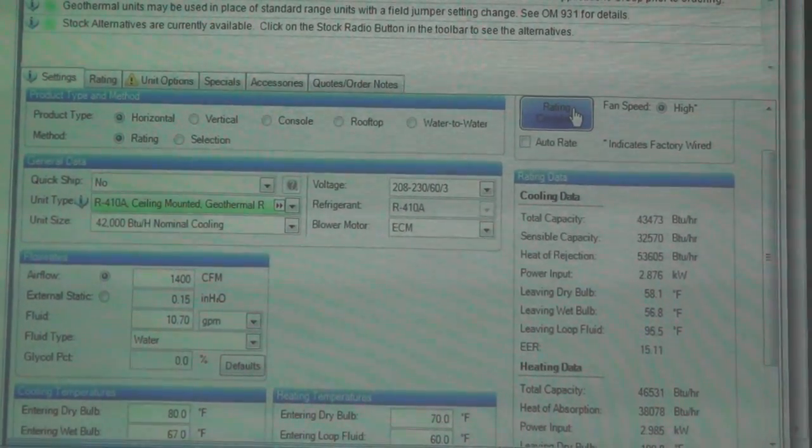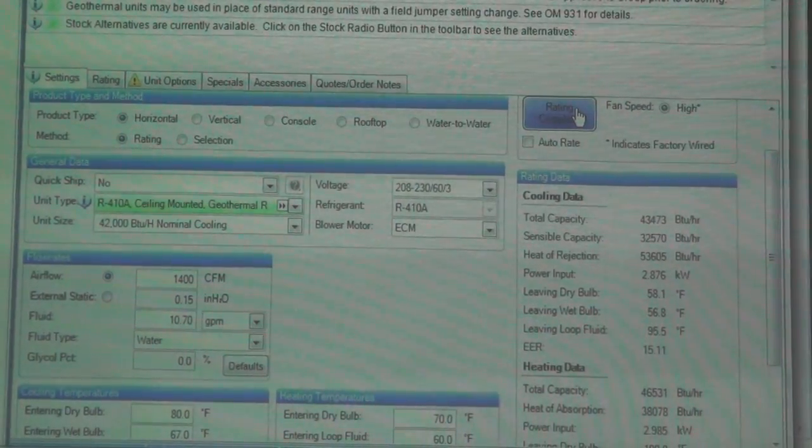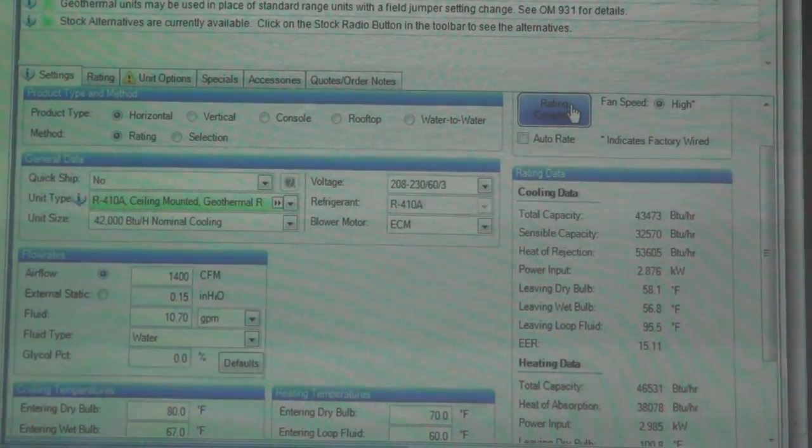What always happens with this refrigeration equipment is you end up trying to calculate your load, which we did. With fan coils and stuff like that, you can pick a fan coil to do almost exactly what you want. That's the beauty of chilled water, which is why we did that one first. As soon as we transfer over into this refrigeration-driven equipment, everything becomes extremely stocked. So now you get an idea of what you want, and then you have to match it to something that these guys make, because they only do certain things. So it's an iterative process. I was going to do one unit, you may have to do two. You may have to split it up, these kinds of things.